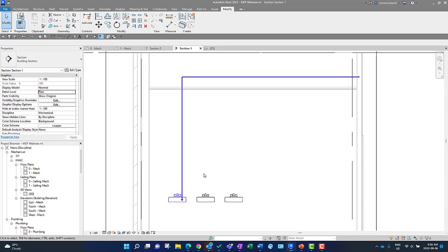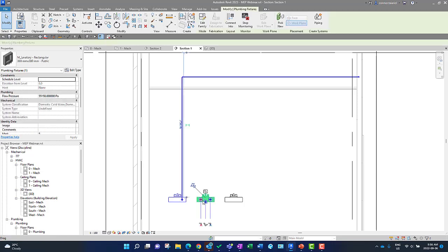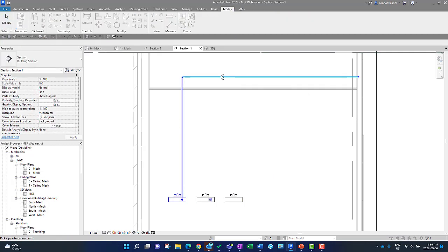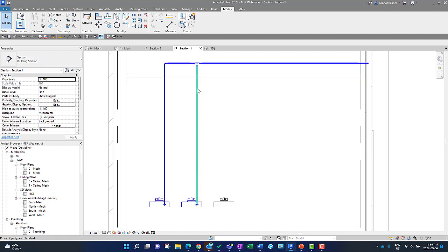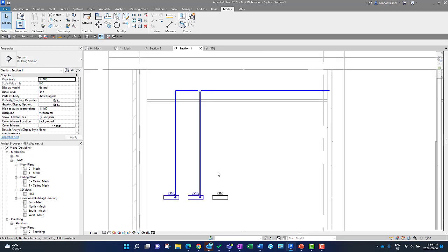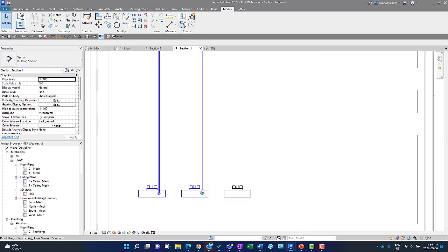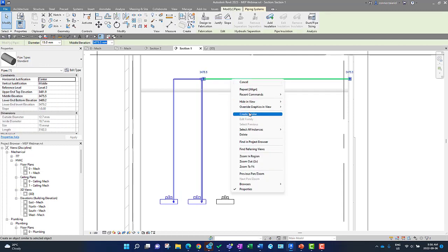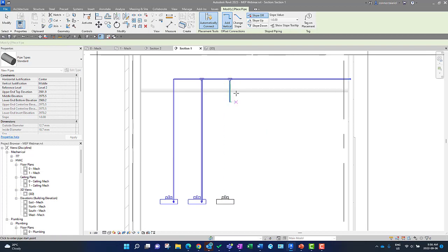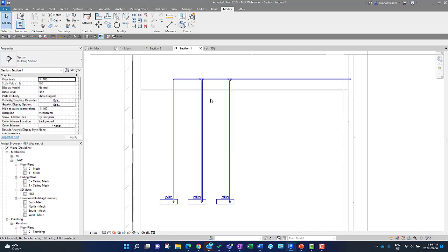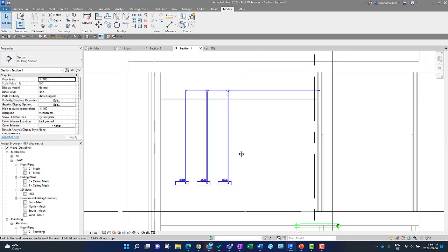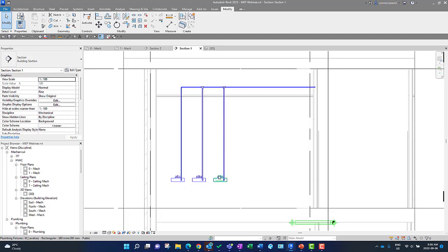We open up that section one more time. Again, we need to lead it down a little bit. If you just select the sink here and go Connect Into, select cold water. This one worked out. Okay, so it'll put in a T, and it gave you the right size pipe going all the way up to the T. Sometimes you might have some inconsistencies with that where it doesn't put it in, or you might get a funky layout. So I always like to just grab my pipe, select it, go Create Similar, and lead it down, and then use your Connect Into tool from that point forward. Again, it'll be kind of trial and error as you get more experience with the workflow. So that is our cold water lines.